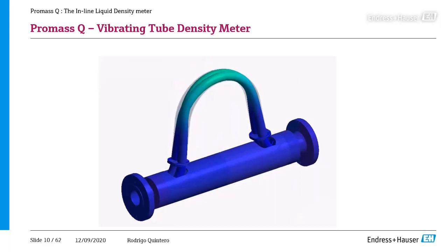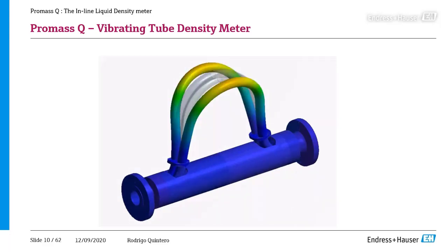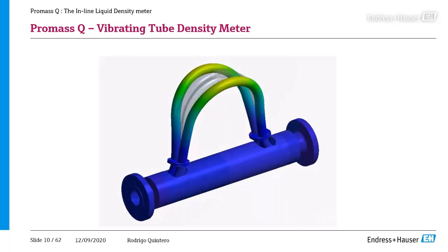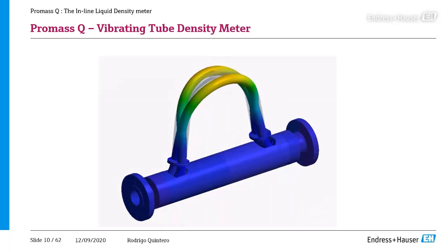So what is going to happen is the sensor will register the oscillation frequency of the tubes, or in other words, more simply, how often the measuring tubes move back and forth in one second. The oscillation frequency is a direct measurement of the fluid density, while the phase shift indicates the mass flow. For example, a tube filled with water will oscillate more frequently than a tube filled with honey, because honey has a higher density. So in other words, once the liquid density changes, the oscillation frequency will change as well. But it's also very important to mention that the density measurement is not based on the Coriolis effect, but on the vibrating tubes. This is very important to see.